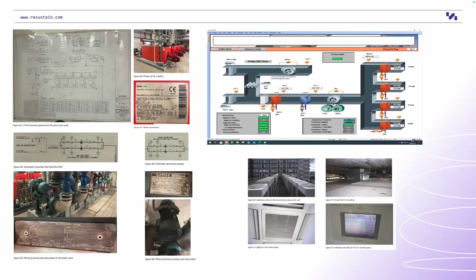This is all the information about the equipment. So we went and found all the equipment, made sure it was all modeled correctly. We modeled all the curves. We looked up all the makes and model numbers, made sure they were modeled as they should be. So not just a single flat line, as it were. The boiler curve was modeled, the fan curves were modeled. Those were all in, and then we calibrated. We used the IPMVP methodology, although I think methodology is in that acronym, so I don't really know how to say it. No, maybe it isn't.